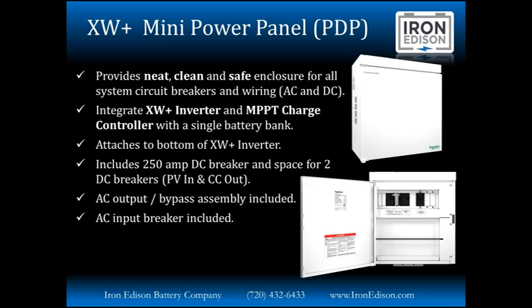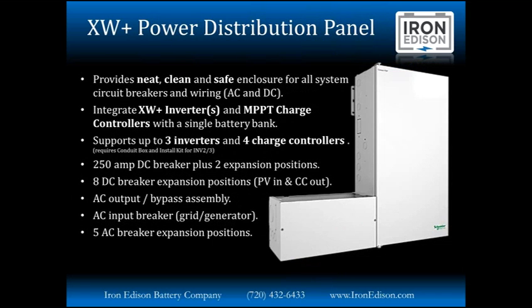So, the mini power panel, again, is great for one inverter and one charge controller. If you're going to be doing a multiple inverter, multiple charge controller application, then the XW Plus power distribution panel is the way to go. Again, nice, clean, neat installation solution to contain all the wiring and circuit breakers. The XW PDP will support up to 3 of the XW Plus inverters, as well as 4 charge controllers. There's some additional conduit box installation kits required for the additional inverters.